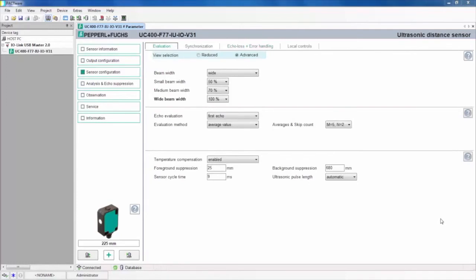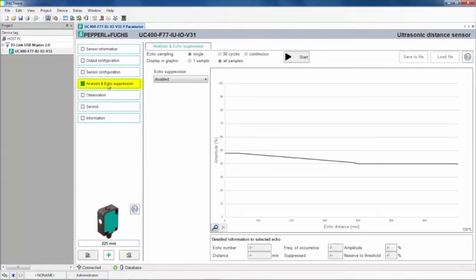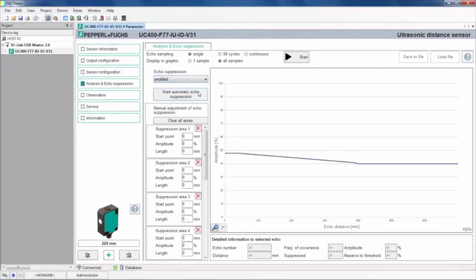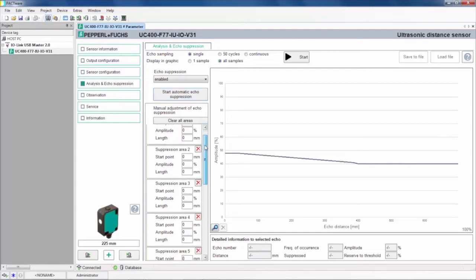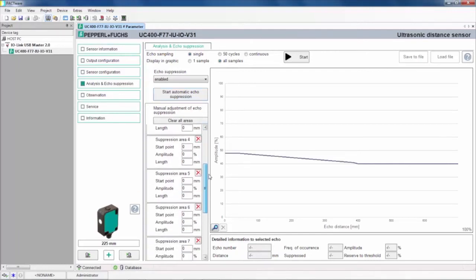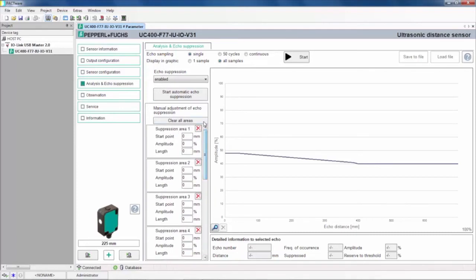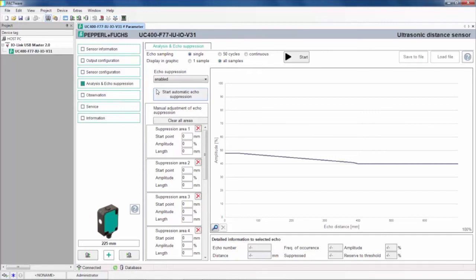The next tab is the Analysis and Echo Suppression window. This feature is the main focus of the demonstration coming up. It allows you to isolate and suppress undesirable echoes received by the transducer, ignoring objects that you don't want to detect. In this tab, you can automatically suppress echoes or manually set up to 10 points to suppress. At the top of the window, you can select how many echoes to sample and how many of those samples are displayed in the graphic. The graphic shows the distance to all objects seen by the sensor and amplitude of received sound from each of those objects. We'll revisit this tab in a moment.